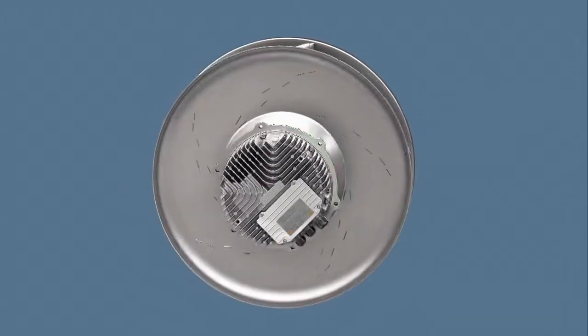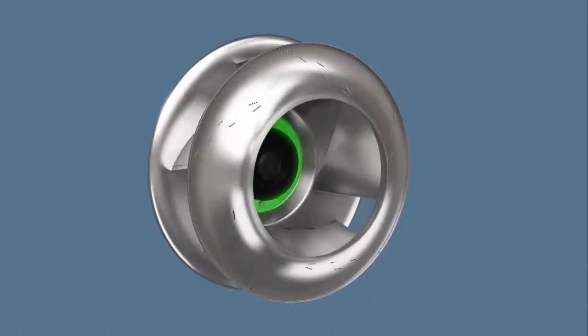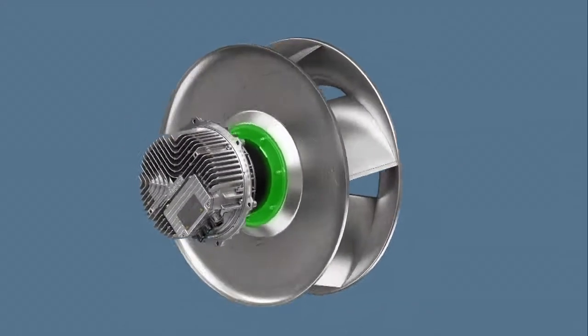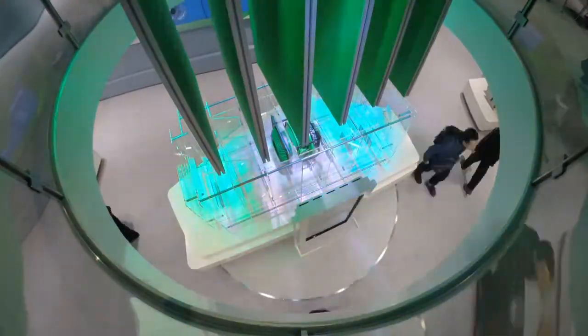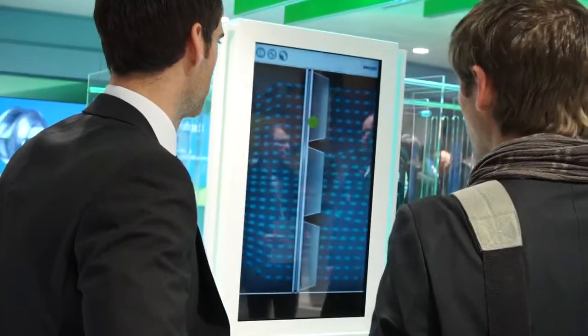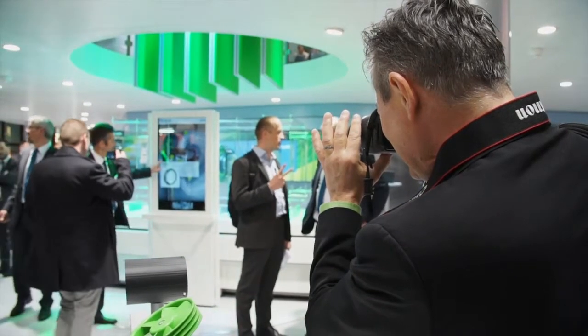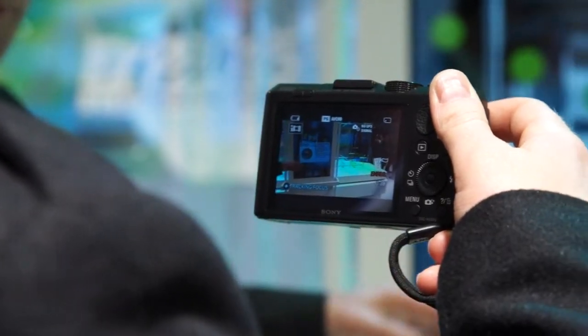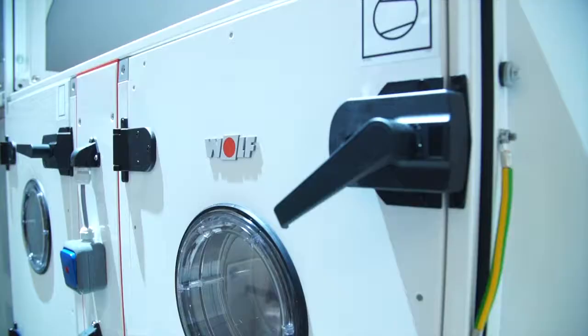Even the motor's position in the impeller was reworked to achieve a good compromise between the compactness of the entire fan unit and the ideal aerodynamic positioning of the motor in the impeller. The result of the optimization? All told, the flow machine redesign achieved an efficiency increase of over 10% for the Radipac fans while also reducing their noise level by more than 3dBA.